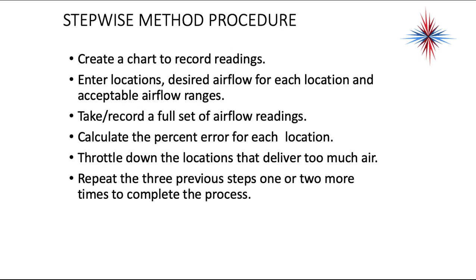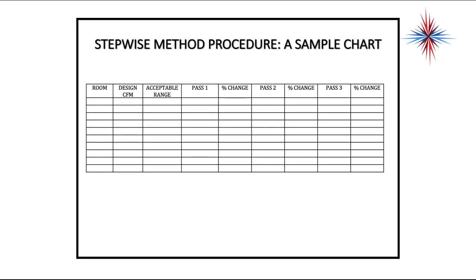For the stepwise method procedure: create a chart to record your readings — normally your company or accrediting organization has charts available. Enter the locations, the desired airflow for each location, and the acceptable airflow ranges. Take and record a full set of airflow readings. Calculate the percentage of error for each location — how much has it deviated from desired. Then throttle down the locations that deliver too much air. Repeat these steps one or two more times. The maximum number of passes in the stepwise method should be three.